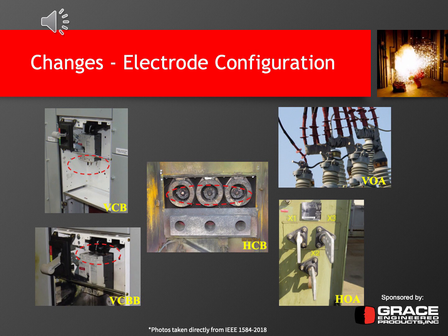In the bottom left photograph, there's the VCBB installation, which is the same circuit breaker, but the cables are now terminating into the top side of the breaker, or the line side of the breaker. And because the breaker itself provides a barrier, that would be a VCBB installation. The middle photograph is an example of an HCB installation, because you have the conductors coming out facing toward the person standing right next to it. And that's shown in the red dotted circle as well.